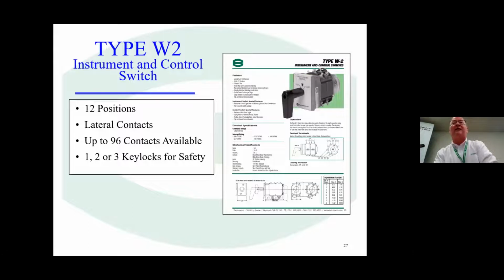But back in the old days, there were instrument and control switches made by Westinghouse, the Type W. And the Type W is the oldest design pretty much in the US for utility grade control switches. And they were very large, and this is one of the devices that we improved upon with the Series 24. But these style instrument switches are still viable, they're still available, they're heavy duty. And this particular switch, it's one of the mainstays of the nuclear industry. The nuclear power plants have used a lot of these Type W switches produced by Westinghouse.